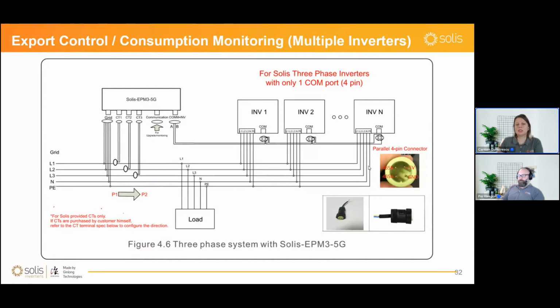In terms of how you would connect an EPM to the inverters, I just want to mention that depending on the type of the inverters, you might have different options. For the inverters up to 20 kilowatt, actually all of our inverters, not just those up to 20 kilowatt, have this 4-pin communication port that you see here. This one has 2 pins for RS485 communication and 2 pins for a 5-volt power supply, where you can actually connect a data logger. You can power and have the inverter communicating with the data logger.